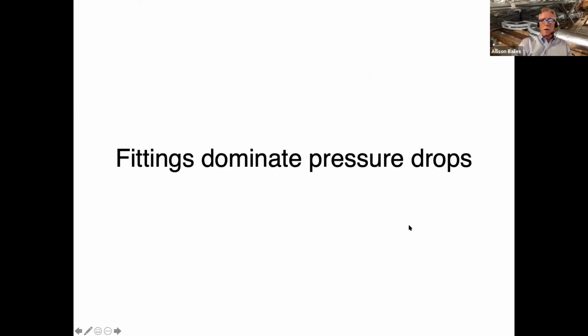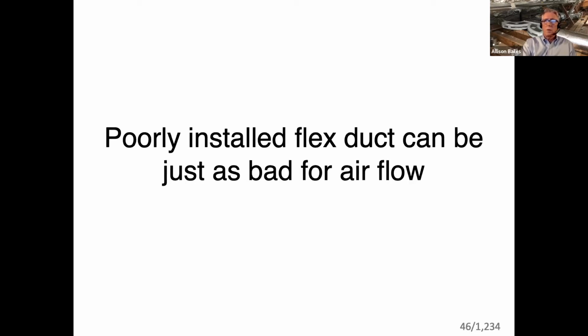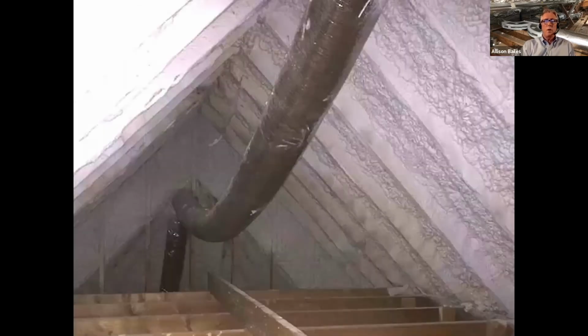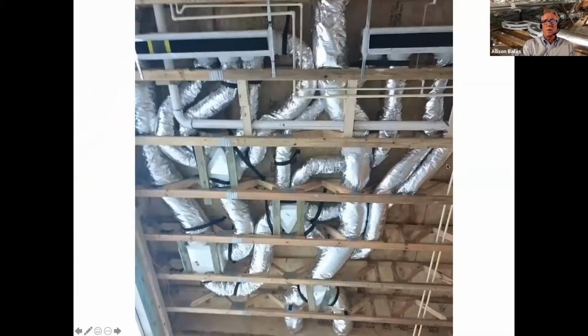So fittings dominate pressure drops, and that's why this myth is not true, because most of the resistance is coming in the fittings, not in the straight duct. So put in good fittings and do your duct design right, and you can have a low static unit that works perfectly. Poorly installed flex, when we're talking about fittings, usually we're thinking of hard pipe, but sometimes people do everything with flex duct and they turn it and split it with flex duct and everything. So you've got to factor that in. It's hard to know what the equivalent lengths are for some of the stuff they do with flex duct. Like, what's the total effective length of this mess right here? That's hard to know.